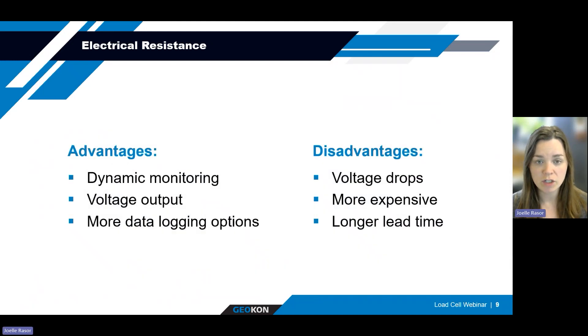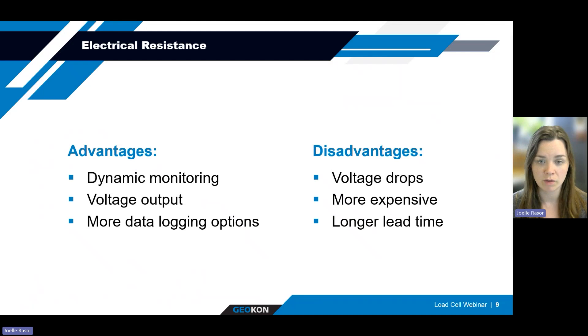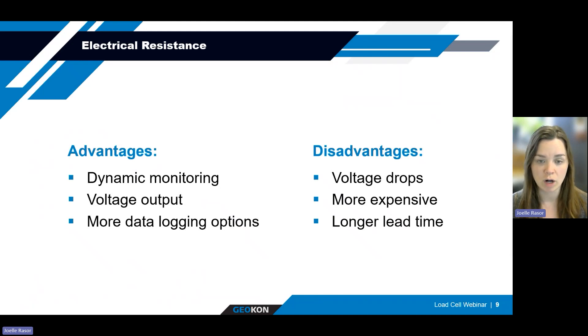Looking at some of the advantages and disadvantages of the electrical resistance load cell: typically it is used for dynamic monitoring as it's a voltage output instrument. They also have a wide range of data logging options and may be a good solution where there's an existing data logger that isn't compatible with vibrating wire technology. Although the voltage output is more universally data logged, a voltage signal will drop over long cable lengths — typically over 300 meters. Additional hardware can be installed at the data logger to overcome this voltage drop if needed. Because of the more complex construction compared to the vibrating wire version, they do tend to be a bit more expensive and can carry a longer lead time.